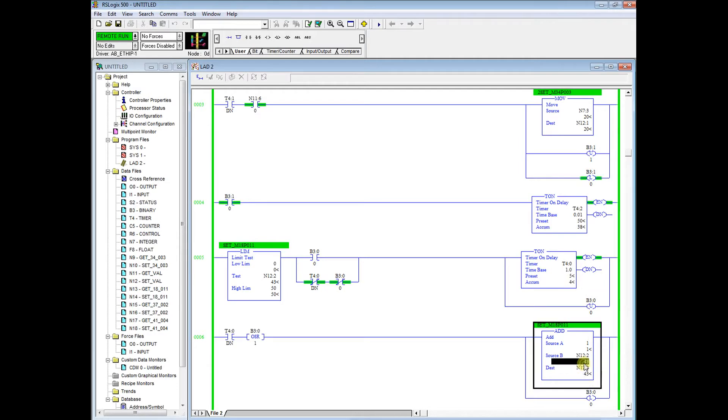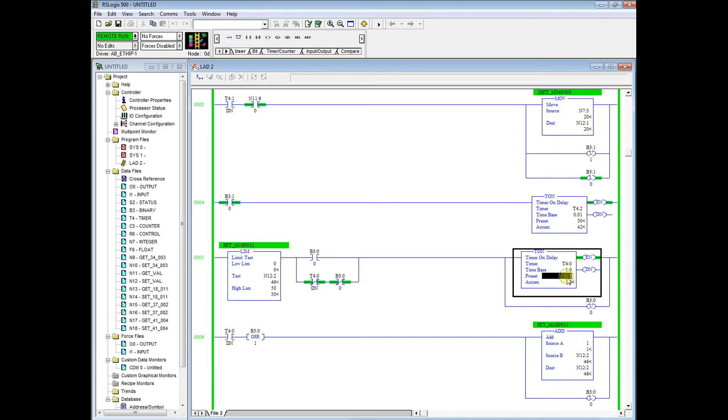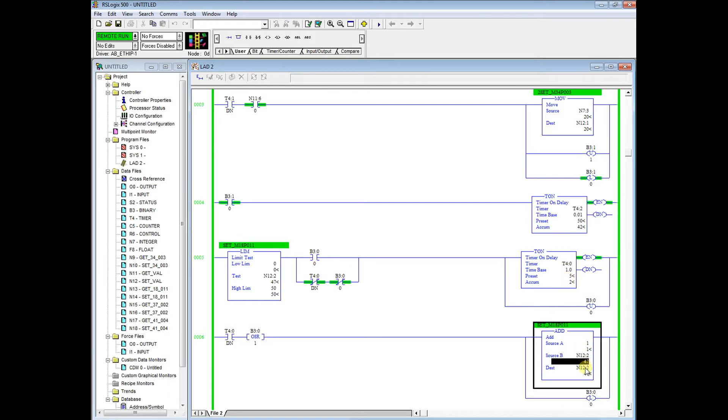Right here we can see 43, 44, we're indexing this parameter up. This is going to be 450 RPM, and every five seconds we have our timer right here preset for 5 and just counting up. Once that's done we increment menu 18-11 up 1 or 10 RPM.